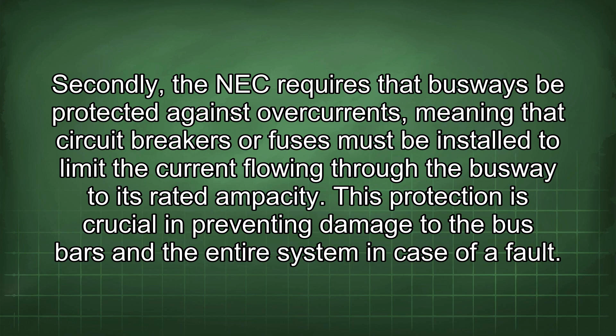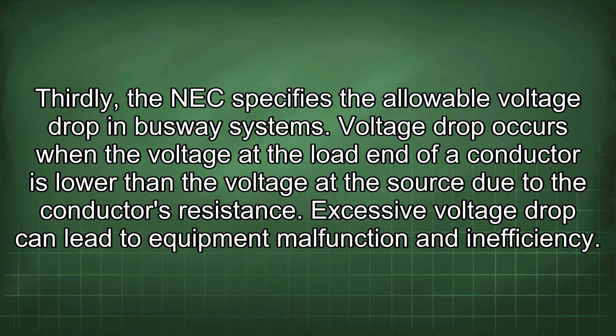Thirdly, the NEC specifies the allowable voltage drop in busway systems. Voltage drop occurs when the voltage at the load end of a conductor is lower than the voltage at the source due to the conductor's resistance. Excessive voltage drop can lead to equipment malfunction and inefficiency. The NEC sets limits on voltage drop to ensure that equipment operates correctly.